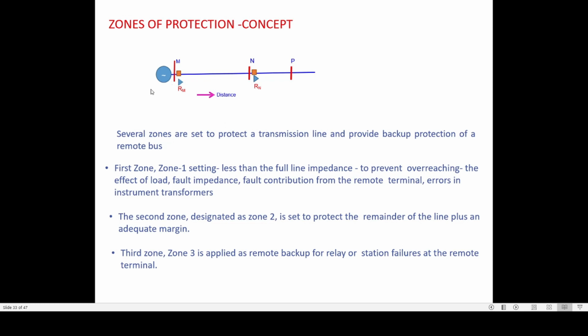for any fault inside this transmission line is not the true representation of the total impedance, because it depends upon the accuracy of CT and CVT, and that accuracy might be either in the forward direction or in the reverse direction. That means if the current is actually 1000 ampere in primary terms, then this relay might measure it at 990 or at 1010.